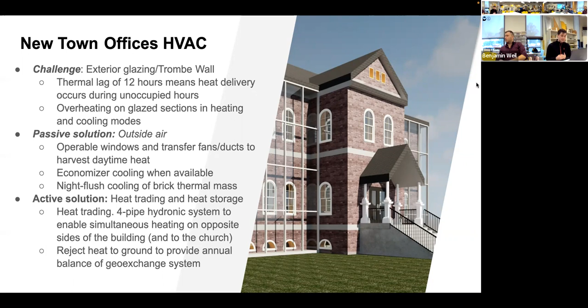The passive solutions Megan explained earlier, but just to recap, they were to have operable windows and transfer fans and ducts to harvest daytime heat, also to use economizer cooling when available, and to use night flush cooling of the brick thermal mass, mainly in the summer. The active solutions are heat trading and heat storage. Heat trading is done with a 4-pipe hydronic system to enable simultaneous heating and cooling on opposite sides of the building, and also provides heat to the church. Heat storage rejects heat to the ground to provide annual balance of the geo-exchange system.